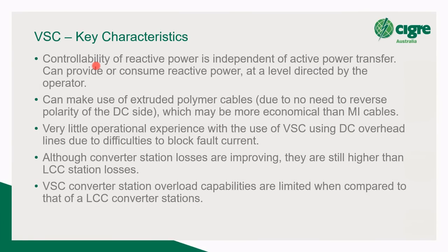The controllability of reactive power is independent of active power transfer, and you decide how much reactive power it consumes. You could sit it at 0 megavars if you wanted to, or you could have it following the voltage, or you could type in 100 megavars and say how fast you want it to ramp, and it'll ramp to that level. Of course, within the power levels. Rule of thumb is 40% of the active power level. That's how much reactive power you've got.